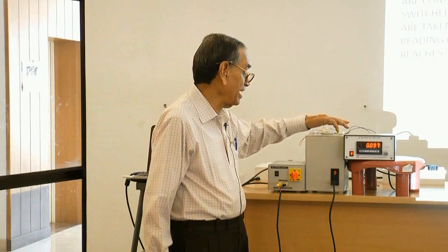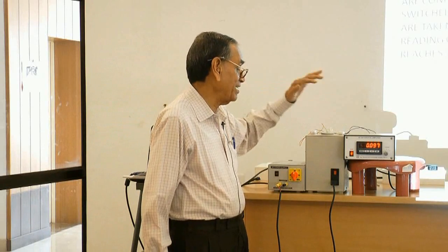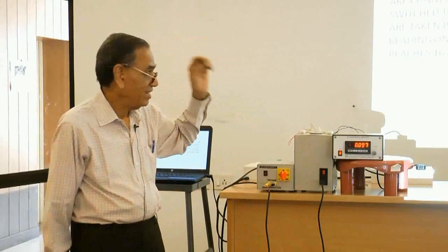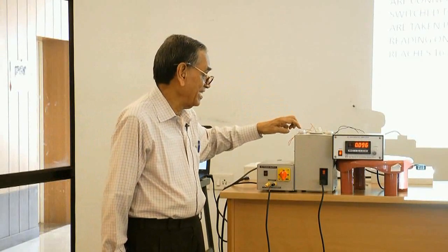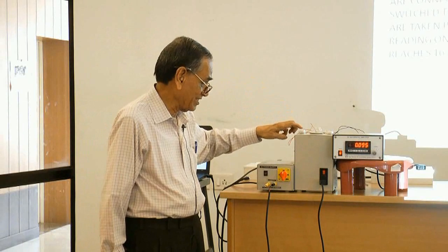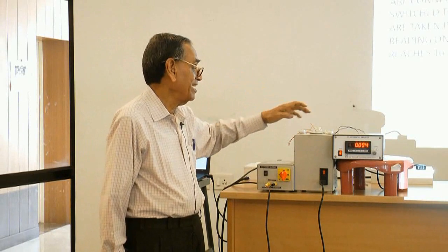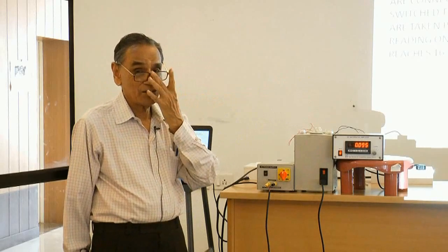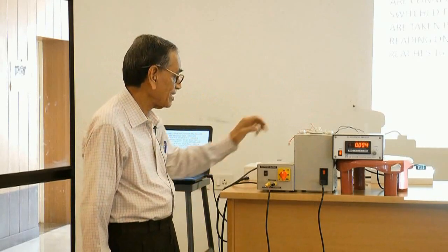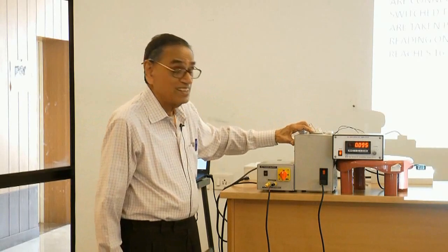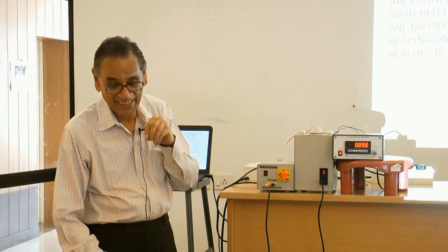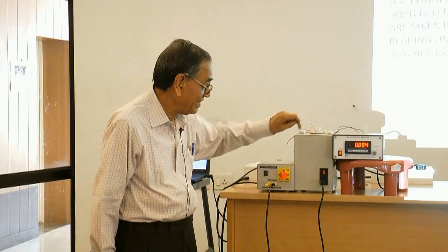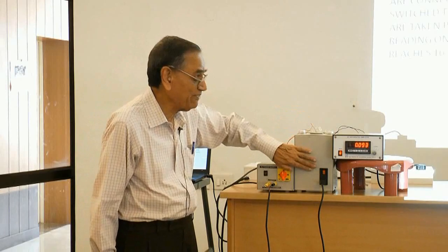We have chromel alumel wire, we have iron copper wire. The iron copper wire is connected to this terminal, and the chromel alumel is connected to this terminal. The 4 wires are welded at the bottom end, and the welded end is hanging inside a furnace.